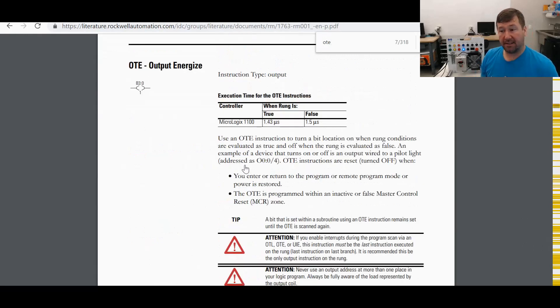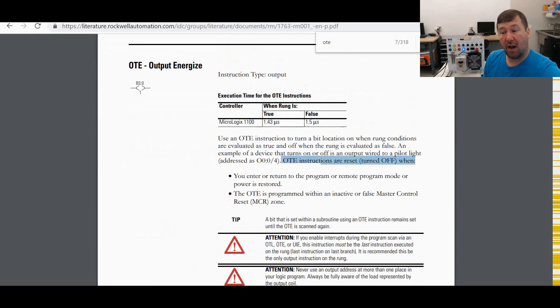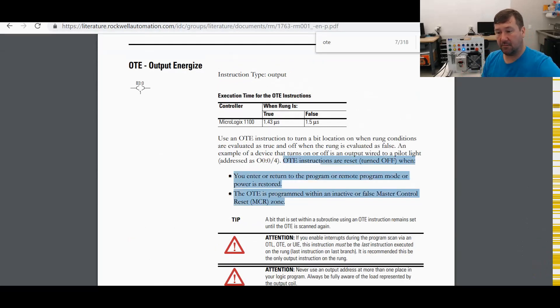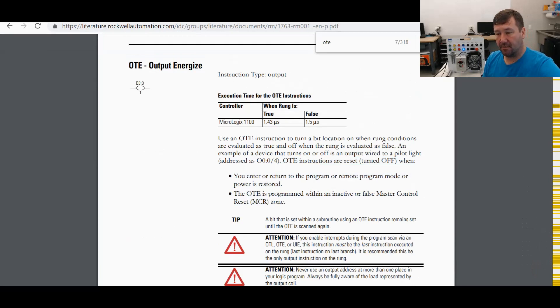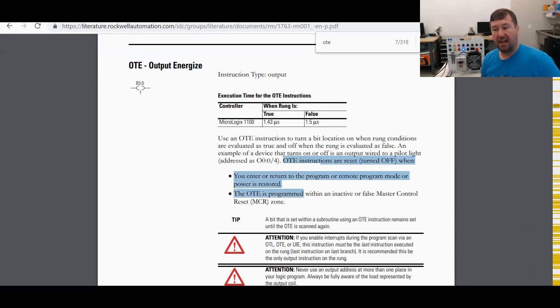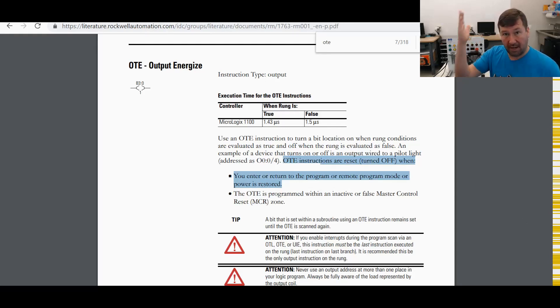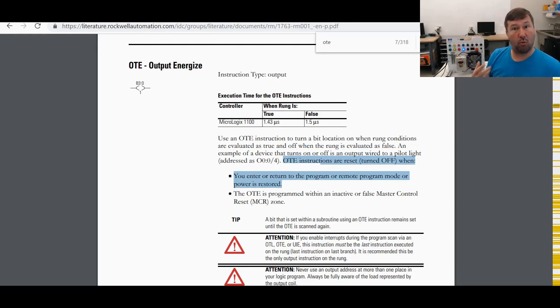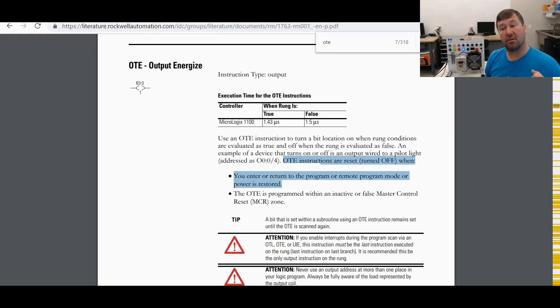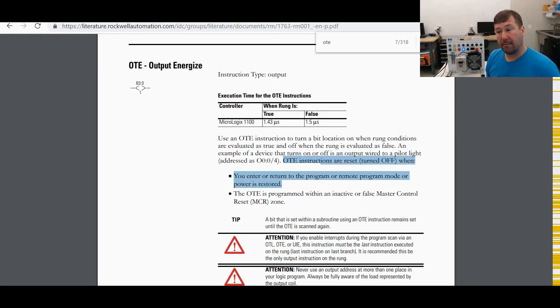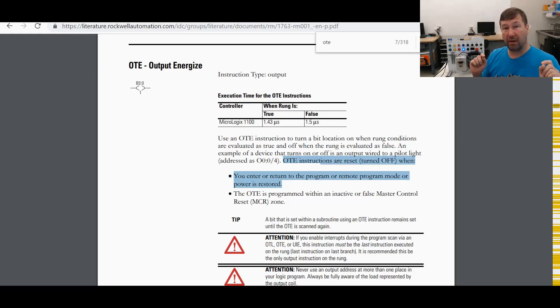This goes through how the OTE works. But right here at the end of this definition, we have this statement here where the OTE instructions are reset or turned off, or it writes a zero to them, when you enter or return to the program or remote program mode, or power is restored.